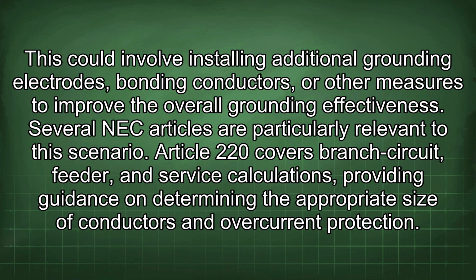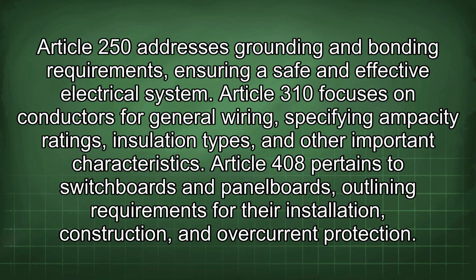Several NEC articles are particularly relevant to this scenario. Article 220 covers branch circuit, feeder, and service calculations, providing guidance on determining the appropriate size of conductors and overcurrent protection. Article 250 addresses grounding and bonding requirements, ensuring a safe and effective electrical system. Article 310 focuses on conductors for general wiring, specifying ampacity ratings, insulation types, and other important characteristics. Article 408 pertains to switchboards and panel boards, outlining requirements for their installation, construction, and overcurrent protection.